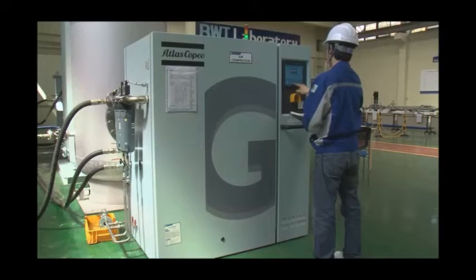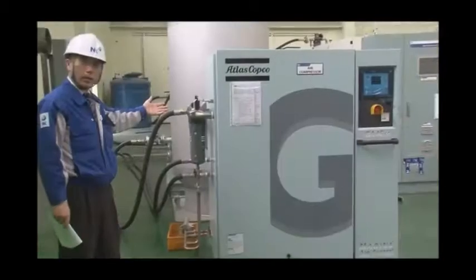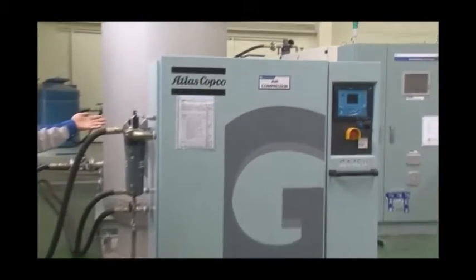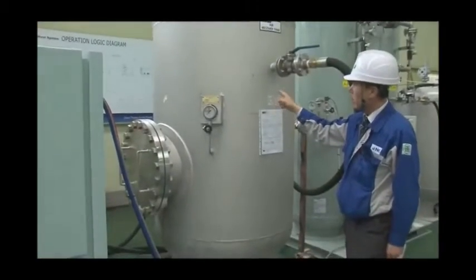For detail safety operation and maintenance, please refer to the operation manual of air compressor. The compressed air is stored in this air receiver in between 4.0 to 6.6 bar, which contributes reduction of pulsation from the compressor and stabilized air flow to oxygen generator.